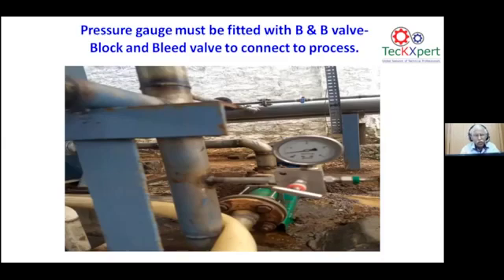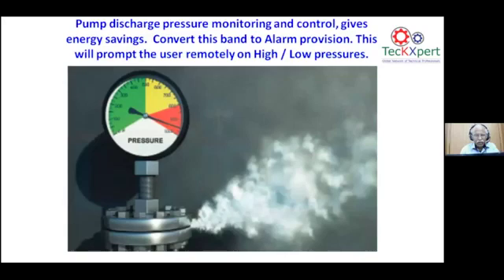This can be checked. So for any of the pressure gauges in your system, on the utility or in the process, you are supposed to have this block and bleed valve. It is a point to have as a standard, as a piping standard. Then on the pressure gauge, what is the green band, what is the yellow band, what is the red band? You have the IoT based system to set the low pressure and the high pressure on your gauge, give a remote alarm, and see that your system is operating at the optimized pressure.